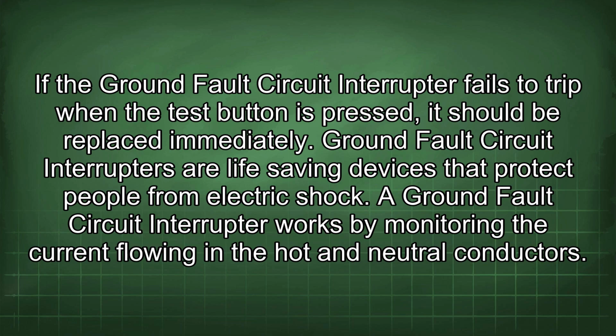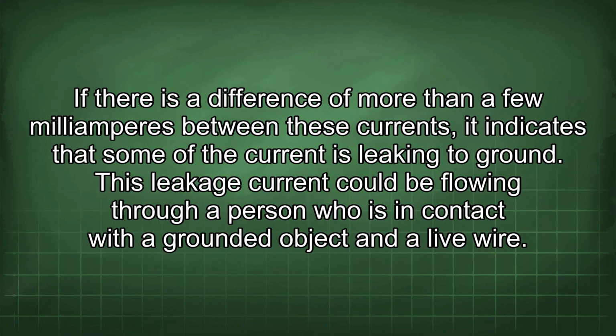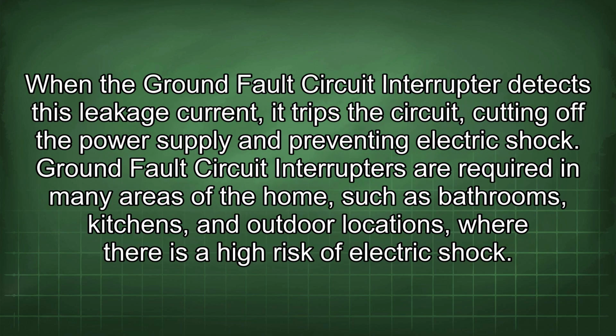A ground fault circuit interrupter works by monitoring the current flowing in the hot and neutral conductors. If there is a difference of more than a few milliamperes between these currents, it indicates that some of the current is leaking to ground. This leakage current could be flowing through a person who is in contact with a grounded object and a live wire. When the ground fault circuit interrupter detects this leakage current, it trips the circuit, cutting off the power supply and preventing an electric shock.